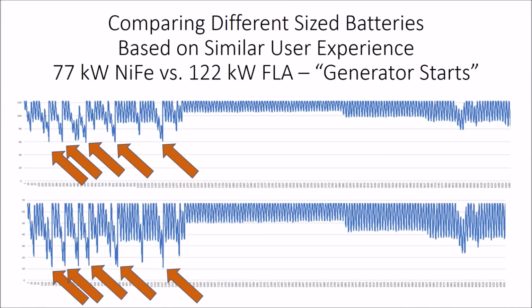Instead of allowing a deep cycle lead acid or nickel iron battery to be fully discharged, we take a generator and, right when the battery reaches the bottom of its absorb phase, turn the generator back on to charge the battery back up. So it never gets into a period of deeper cycling. We use that metric—how many times the battery needs to rely on the generator to take it back to the top—to compare a deeper cycle battery to a shallower cycle battery.